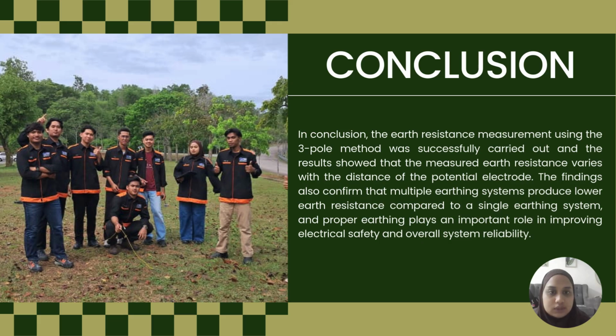ground. In conclusion, the earth resistance measurement using the 3-pole method was successfully carried out, and the results showed that the measured earth resistance varies with the distance of the potential electrode. The findings also confirm that if we use a multiple earthing system, it can reduce earth resistance compared to a single earthing rod. So that's why we get the best result, which is using parallel with 3 rods. And lastly, proper earthing plays an important role in improving electrical safety and overall system reliability.